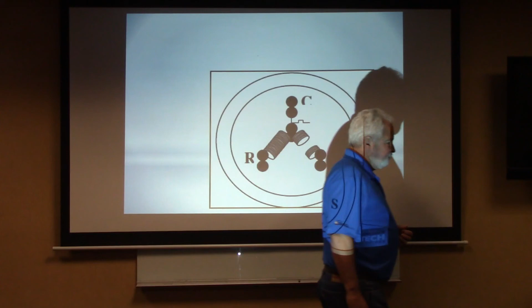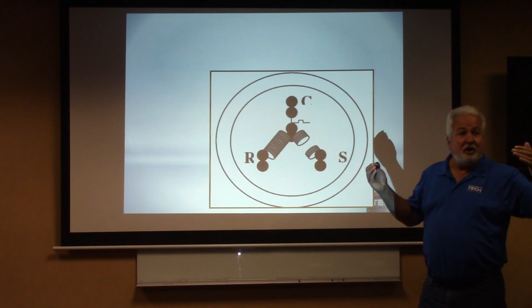Open start winding, everybody okay with that? Good, because you guys are going to start sending compressors back that are under warranty, and they're going to say it was not. What do you typically write down when something's wrong with a compressor? Grounded, or bad? There's no bad compressors. They're either open, shorted, or grounded. Give me that information, because when you just say it was bad and they don't see that on their check sheet, they send it right back down, and whose money is tied up that whole time? Yours. So let's get our terminology right.